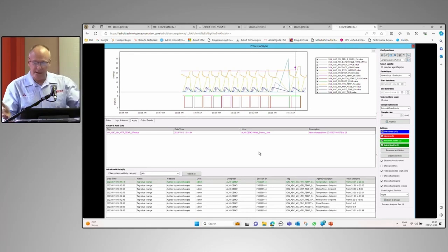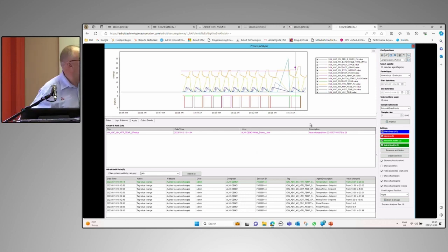That's fine. And if you run it now, you'll see that we won't have that problem. So you can see here the smart UI audit. Someone in the operator changed the heater set point at that time, and they changed it from 23 to 28 to 26. And then you'll see, in fact, the process has gone away. And that's when you would adjust your recipe or whatever you need to do to bring the process in line.